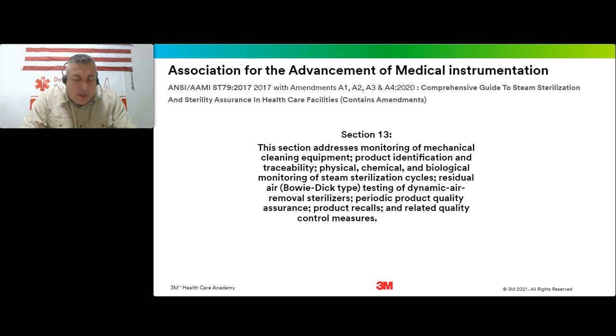A3 speaks to the frequency of cleaning sterilizers and routine maintenance, which we will cover later in one of the slides, a very important element. Your sterilizer maintenance is very important. A4 addressed the BI lot numbers, just the matching of the lot number to the test you're using and the recording of such. So heads up on that.